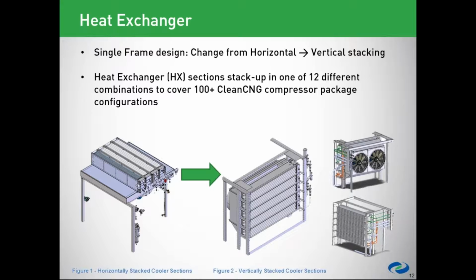Next slide is the heat exchangers setup. We've gone from a horizontal, what we used to call a cooler section, to a vertical stack section, and it's very easy to maintain this piece of equipment in the fact that we remove a small amount of tubing off the ends of these things and undo 4 bolts on the back of each of the sections, and we're able to slide these out and actually pick them up with overhead crane if we want.